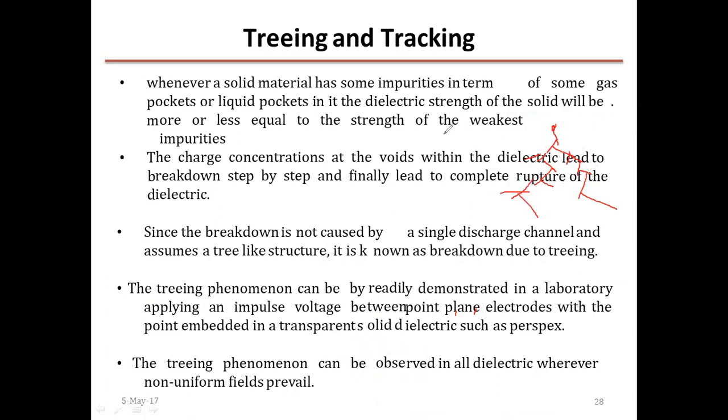Okay, so that is why it is called the tree effect, and that hotspot actually occurs because of the breakdown of the solid dielectric. And as we know that solids are not fluids, the solid particles cannot be replaced by fresh particles. Okay, so the charge concentration at the voids within the dielectric leads to the breakdown step by step and finally leads to complete rupture of the dielectric.